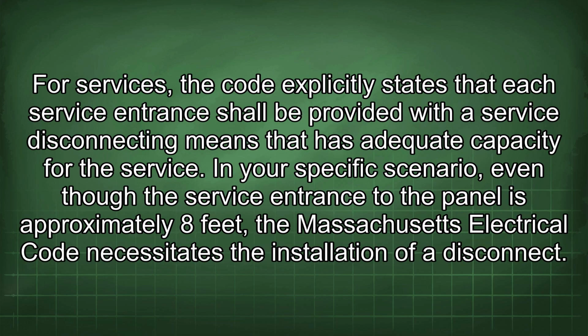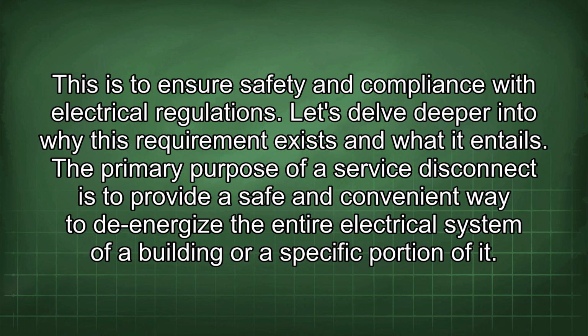For services, the code explicitly states that each service entrance shall be provided with a service disconnecting means that has adequate capacity for the service. In your specific scenario, even though the service entrance to the panel is approximately 8 feet, the Massachusetts Electrical Code necessitates the installation of a disconnect. This is to ensure safety and compliance with electrical regulations. Let's delve deeper into why this requirement exists and what it entails.